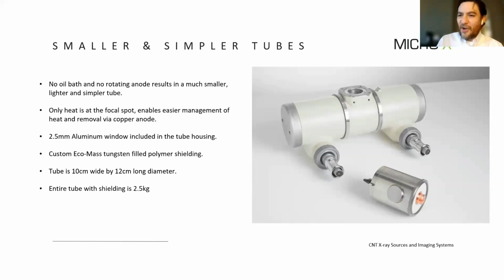What that means is the only heat in the system, and it is a lot of heat, is at the focal spot. But because the only heat is at the focal spot, we're able to draw that heat out and manage it differently. So it means that we don't need a glass insert tube in a big oil bath. This image is meant to really show the comparison in size between the entire tube assemblies.